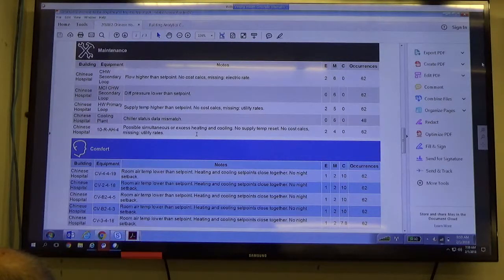There's another big one that Building Analytics finds: possible simultaneous or excess heating or cooling, no supply temp reset. Simultaneous heating or cooling is calculated by measuring the inlet air temp versus the outlet air temp. So if the mixed air temperature is say 65, and on the supply side the heating and chill water valves are closed, but we gain 10 degrees, it's going to flag it and say, check your hot water valve for leaks, calibrate your sensors, check your sensor locations, etc.